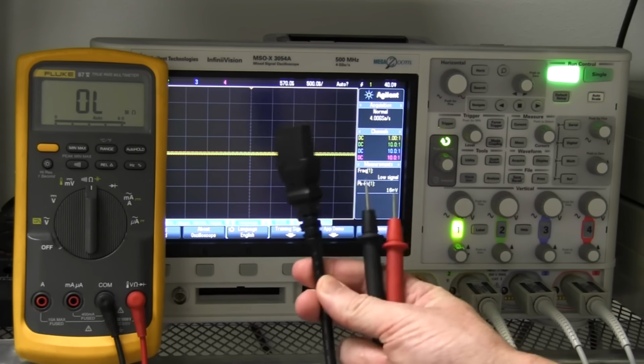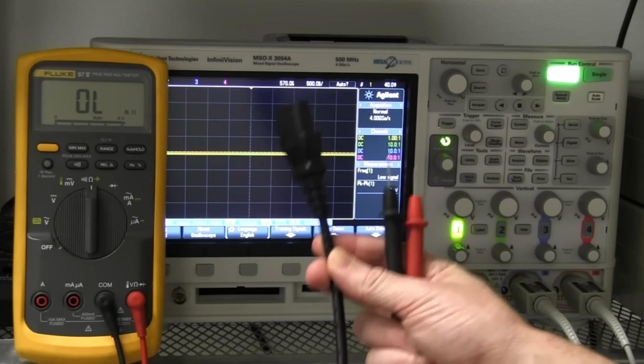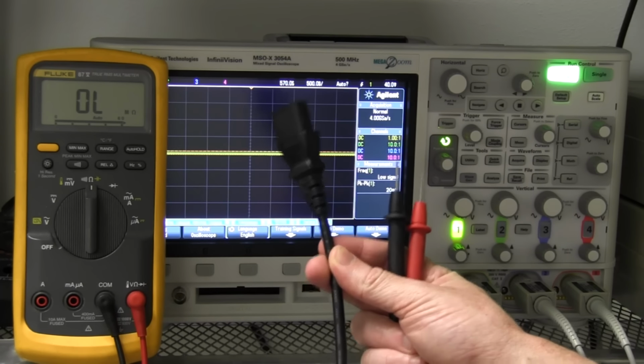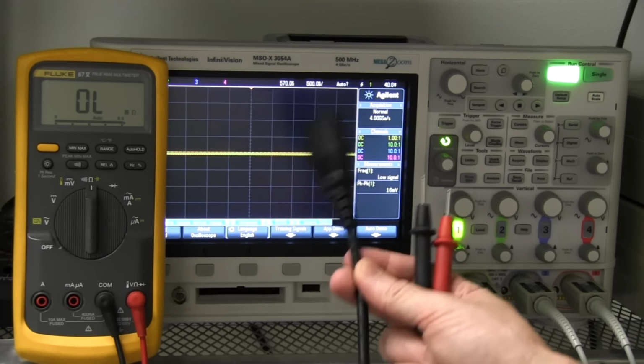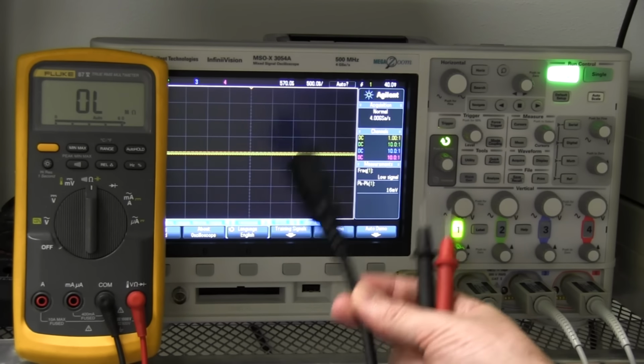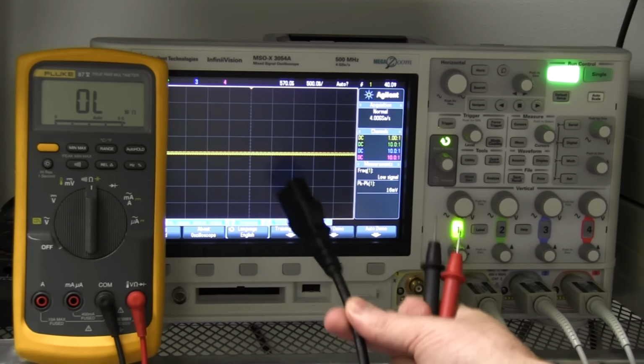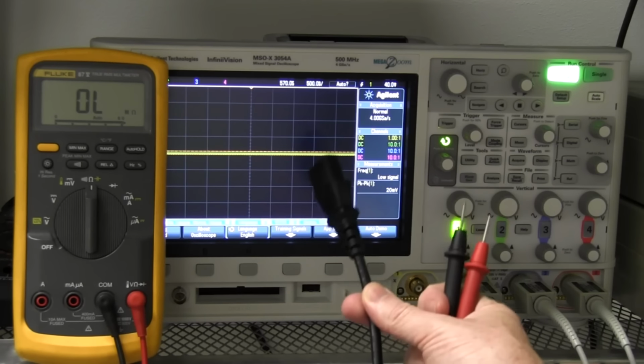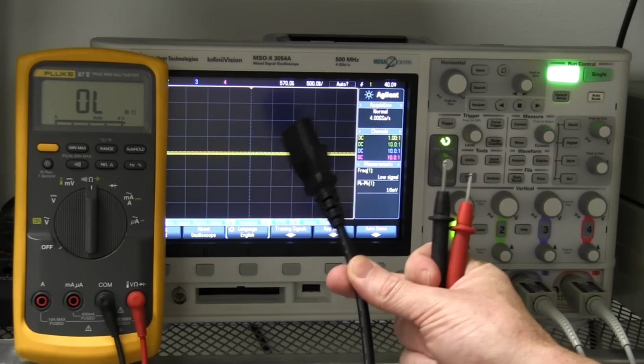So if I've got a power cord, here's an IEC power cord, it happens to be plugged into the same power board as this oscilloscope, but it doesn't have to be. It can be on the opposite side of the room, the opposite side of the house or factory or whatever. The mains earth will be common and tied together throughout the whole system.